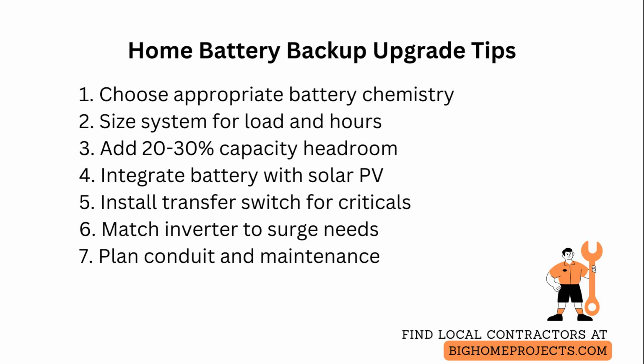Include a manual or automatic transfer switch to isolate and power only critical loads during an outage, which keeps inverter loads within rated capacity and complies with electrical code. Specify a whole system that matches inverter continuous and surge ratings to motors and HVAC startup currents, and consider stacked or parallel inverters for future capacity increases.